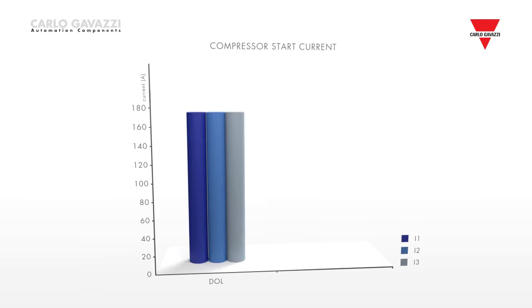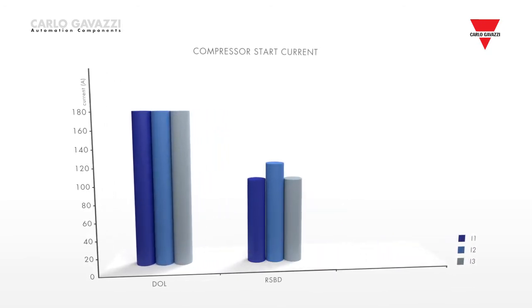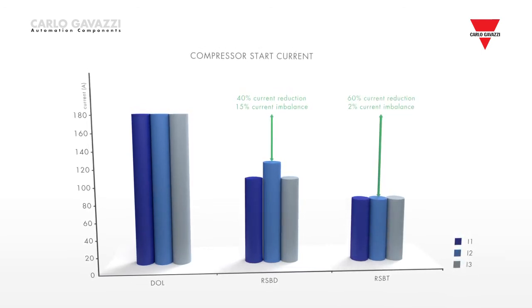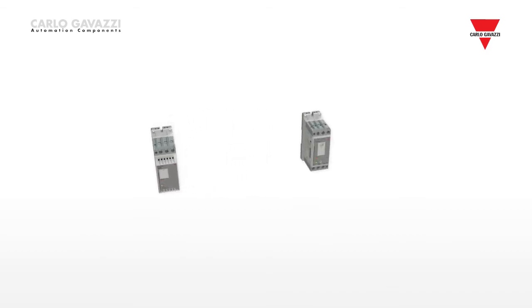The self-learning algorithm in the RSBD performs two main functions. Firstly, current reduction, which is typically around 40% when compared to a direct online start.